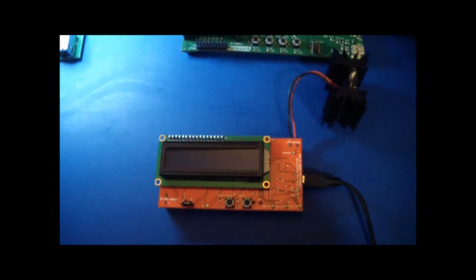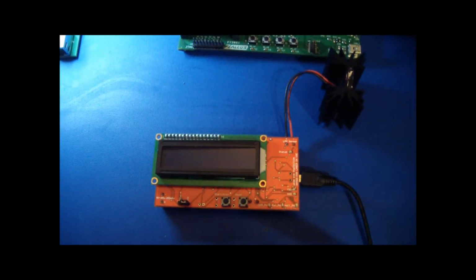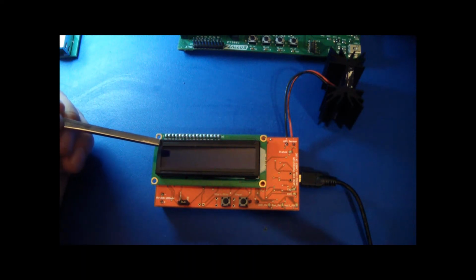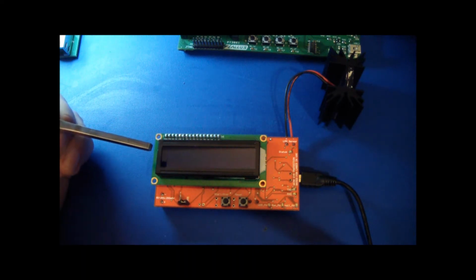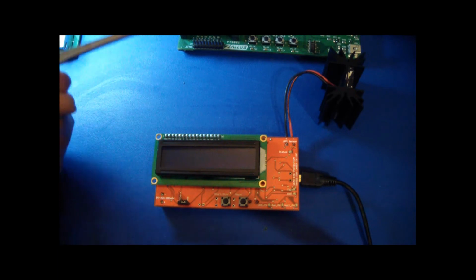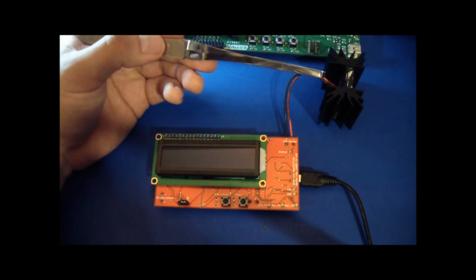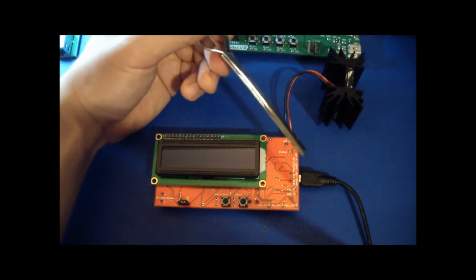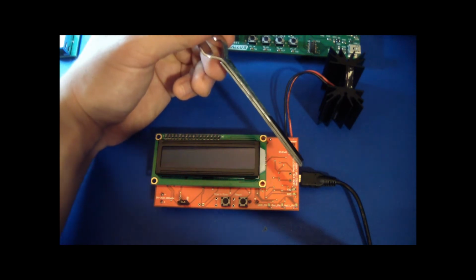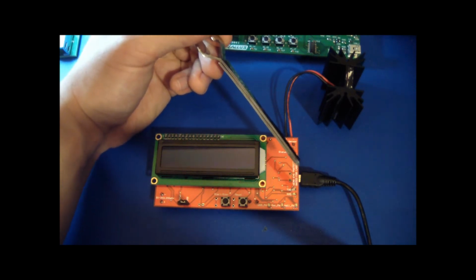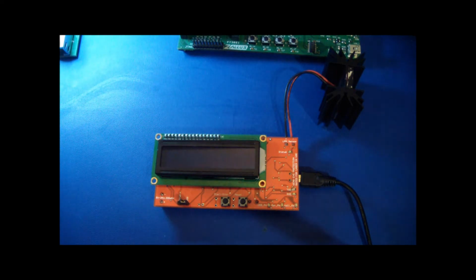So this laser power meter has a couple nice and unique features to it. It has a 16 by 2 LCD display. It has a Peltier cooler sensor, as well as a USB interface for data logging, as well as USB power. However, that is not to say that's the only way it can be powered.